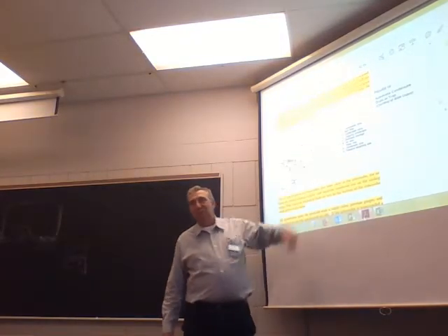I've seen receivers rot right out. When moisture sits there, it's going to rot the heck right out. You have to go around and test things. You still have to be part of PMI to make sure those drains aren't plugged themselves, right?